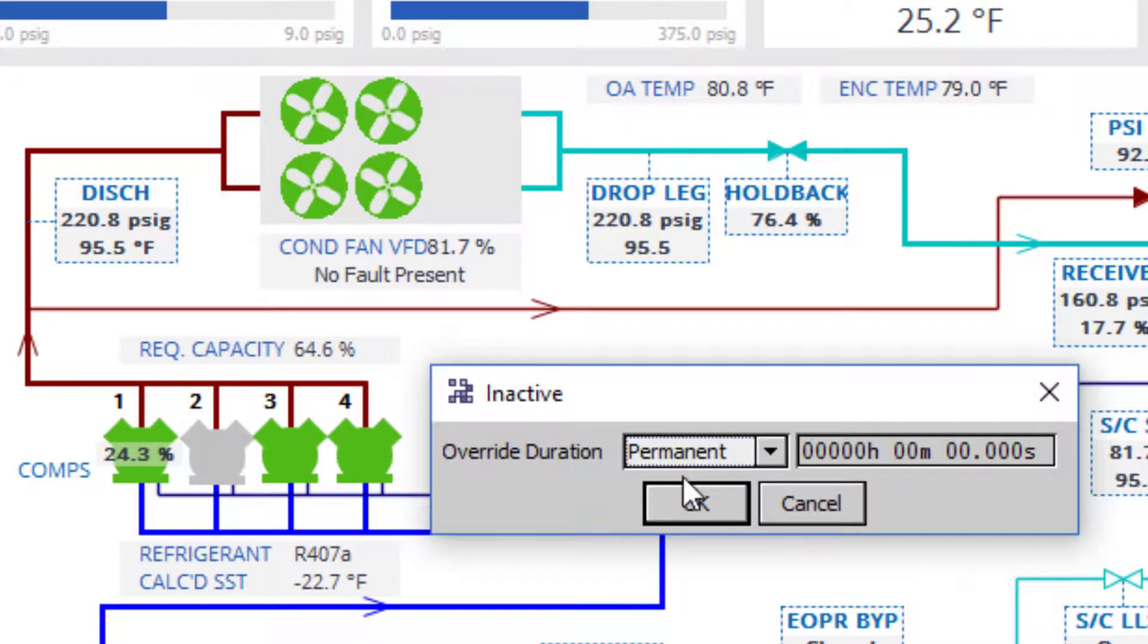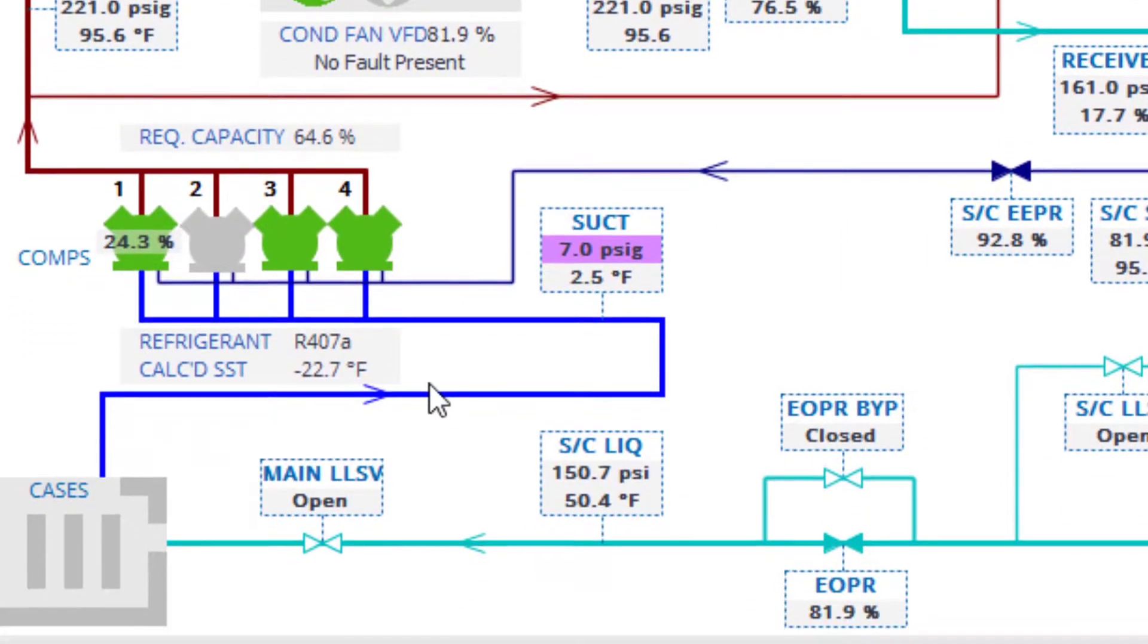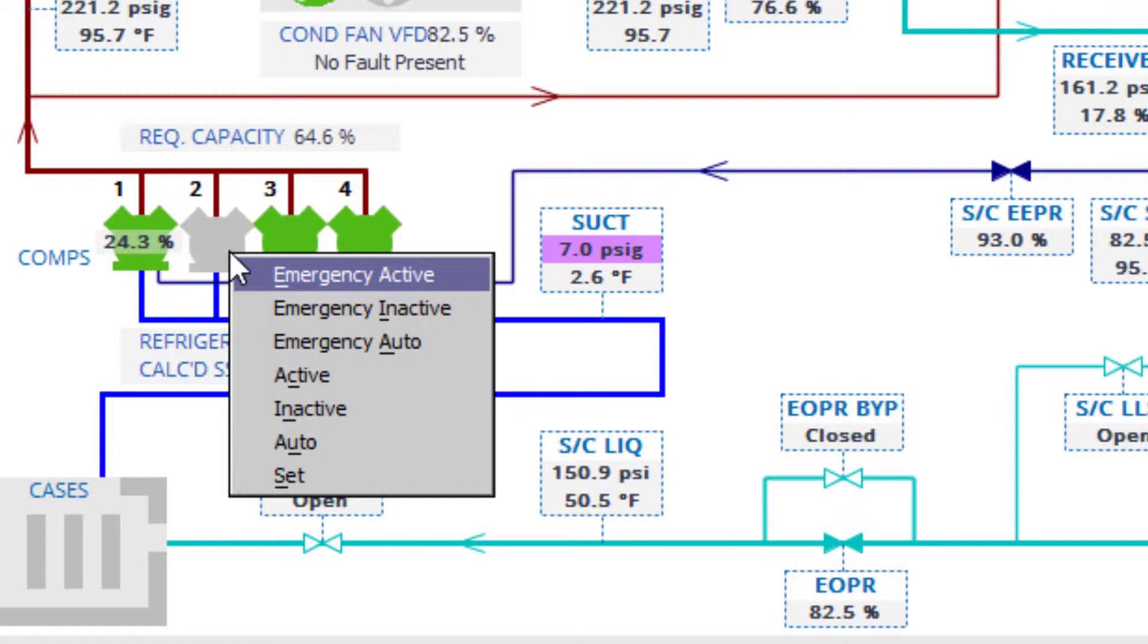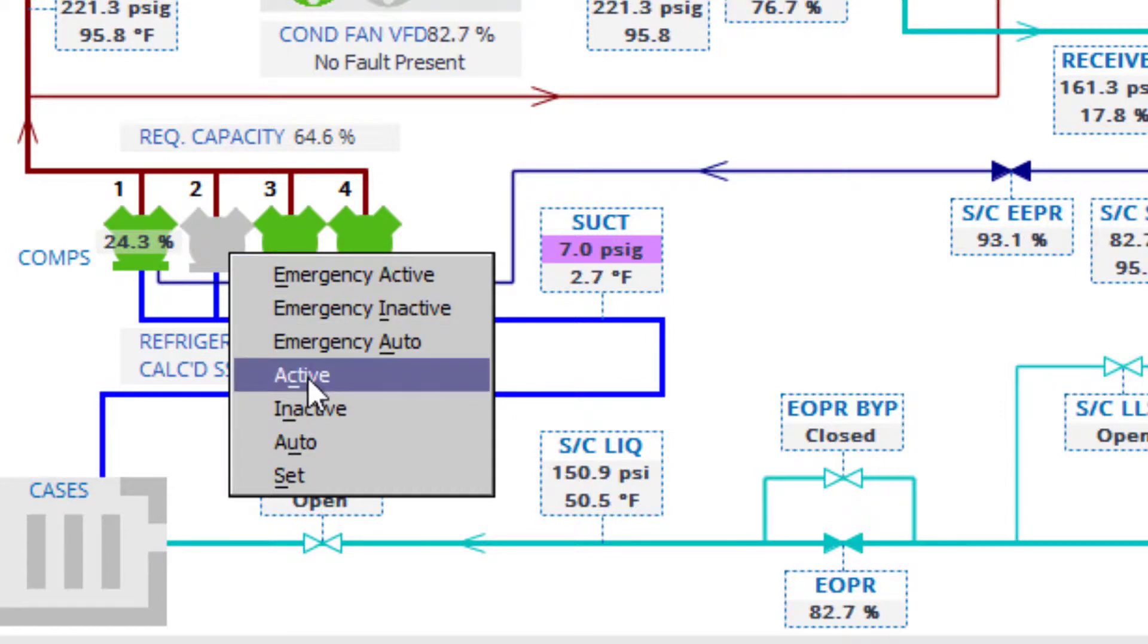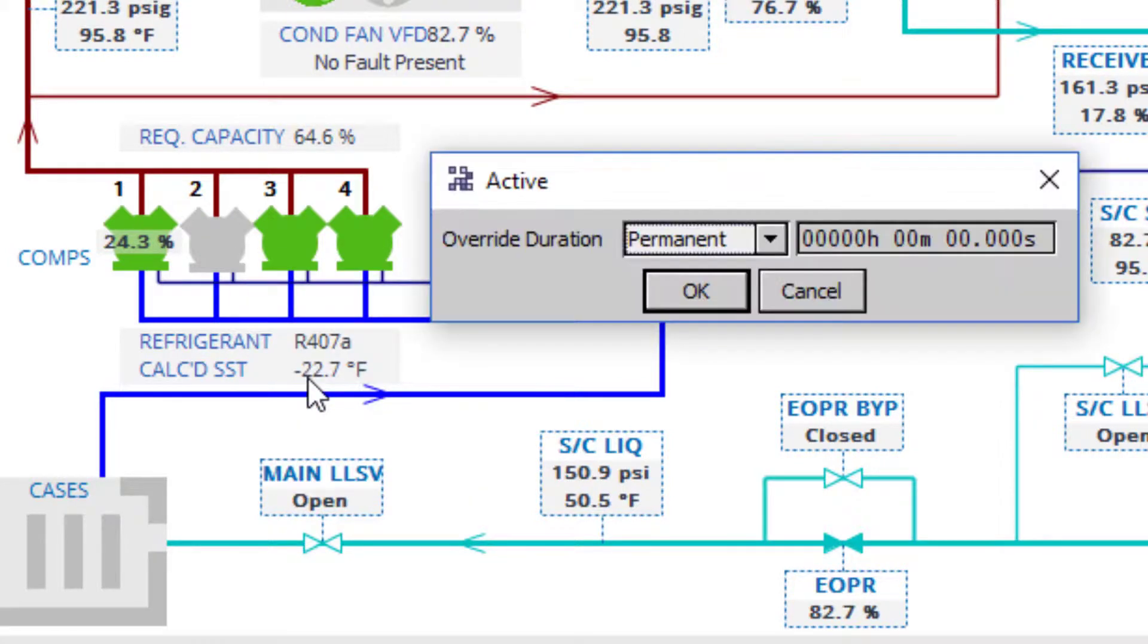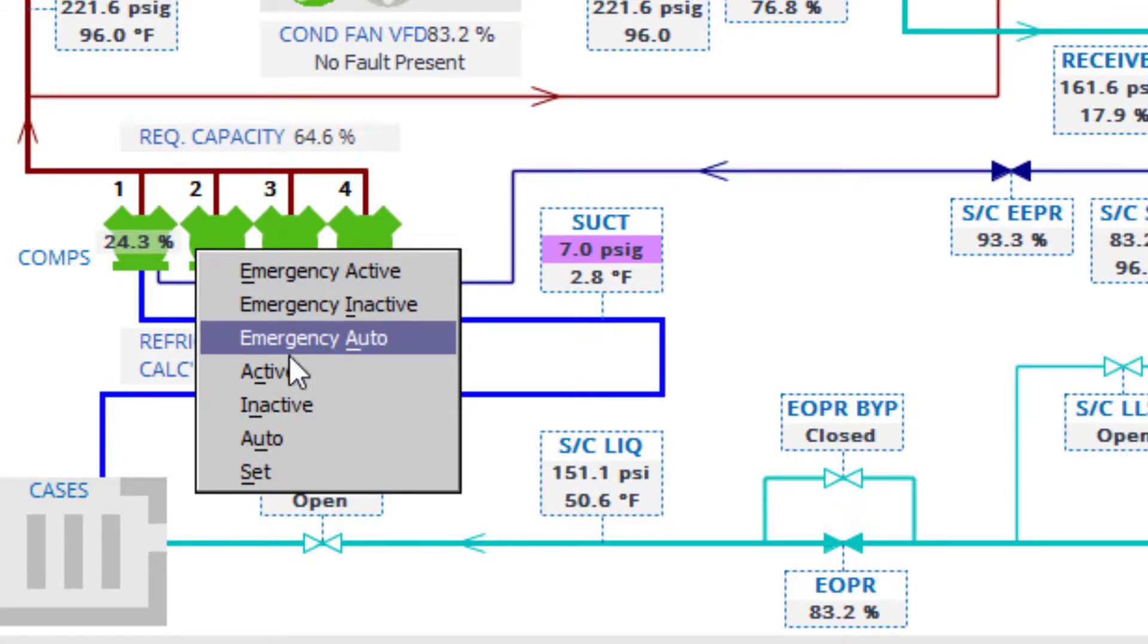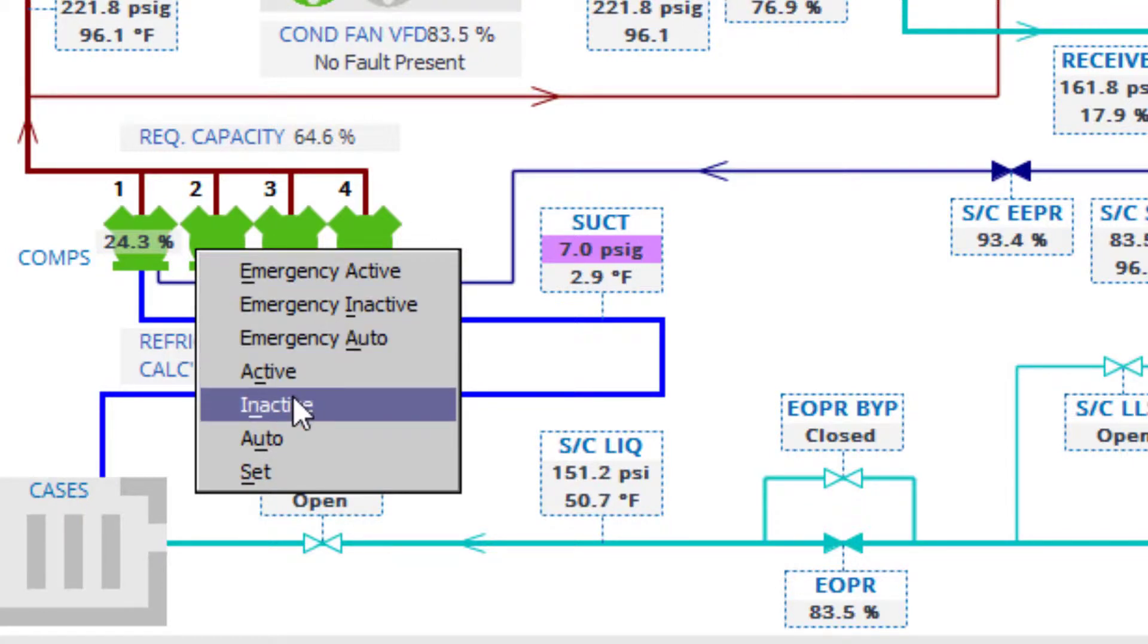Another common graphical override is with the compressors. Simply right-click on the compressor graphic and select active for a compressor to turn on, inactive for it to turn off, or auto which will resume normal algorithmic operation.